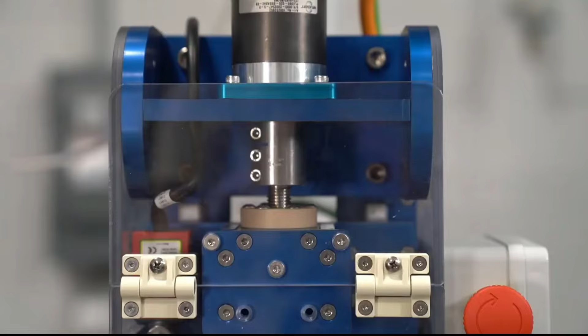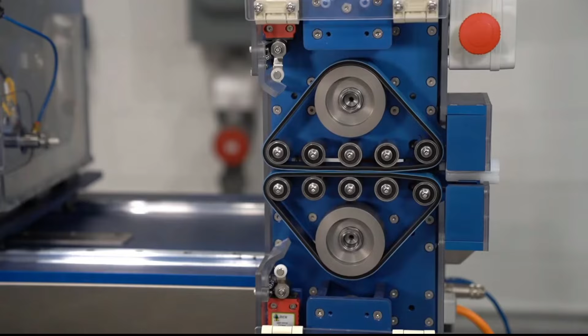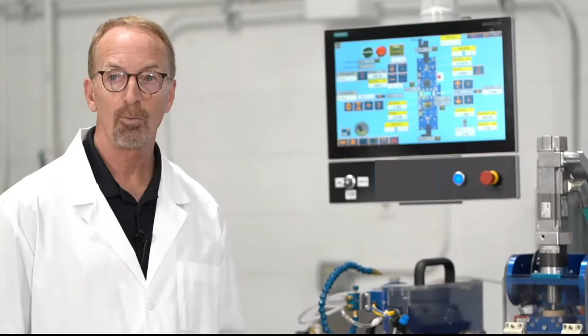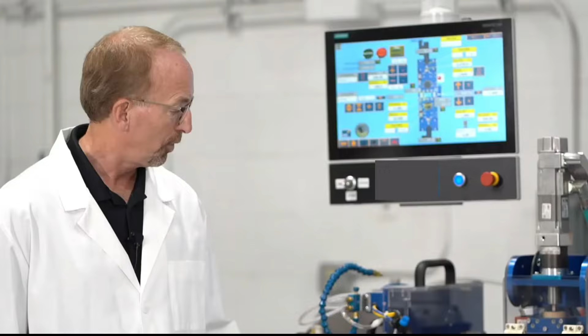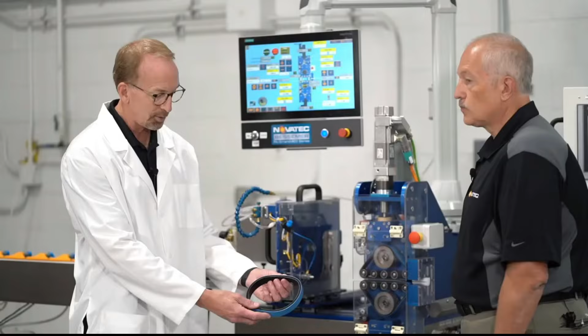Now we're going to talk about a specific medical design puller. Everything we've done here was specific, especially for making what I call microbore tubing, small tubing, say a 1/16 of an inch and below, down to 5 or 10 thousandths with a 1 or 2 thousandths wall. You'll notice the belt traction length is much shorter, and the rolls are down below the two end rollers, so you have a controlled nip point.